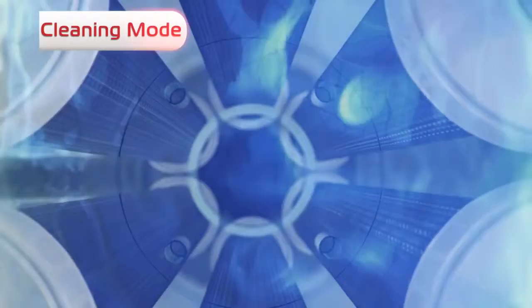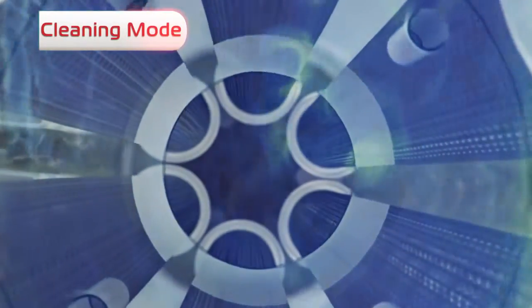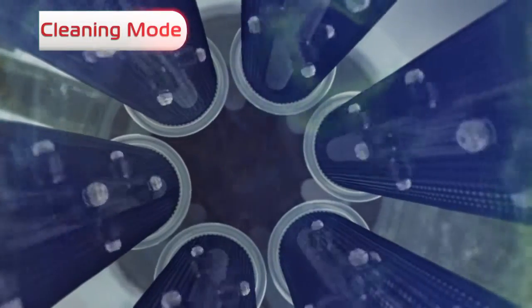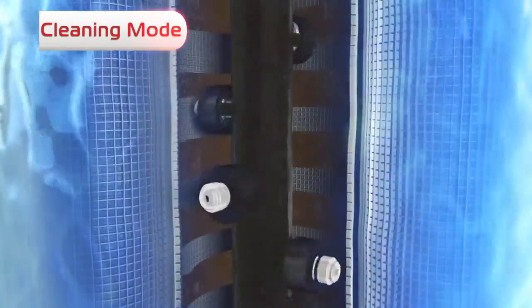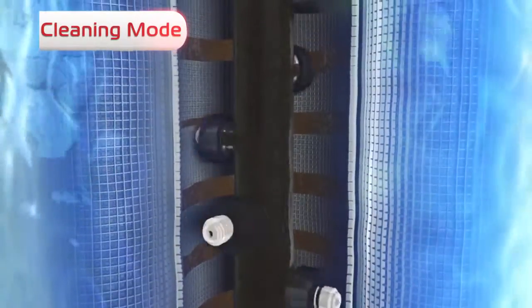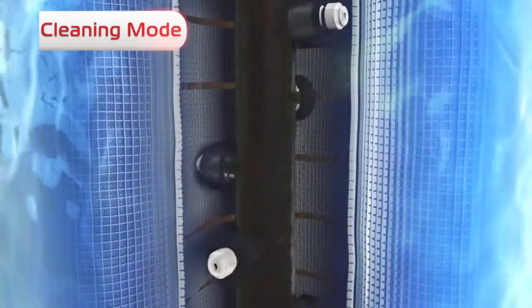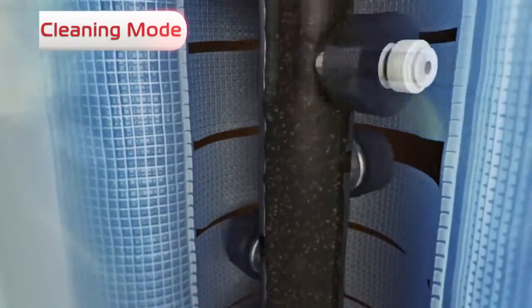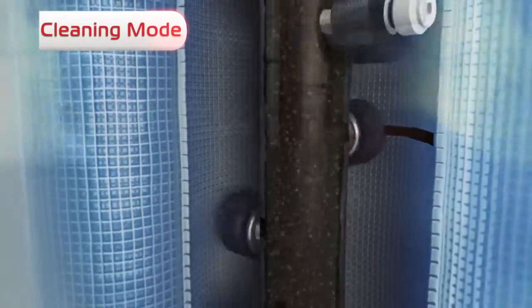The motor drives all six scanners simultaneously in a helix path by means of a central threaded shaft. The resulting reverse flow through the SLN creates a high-force suction effect at the suction scanner nozzles, effectively removing the suspended solid particles from the screen through the flushing valve.